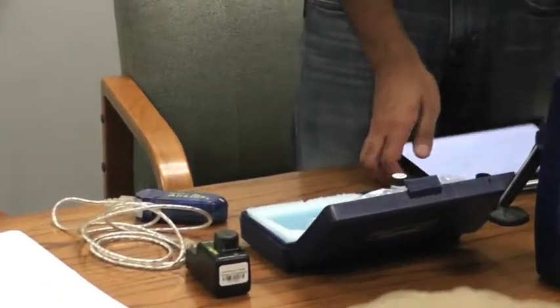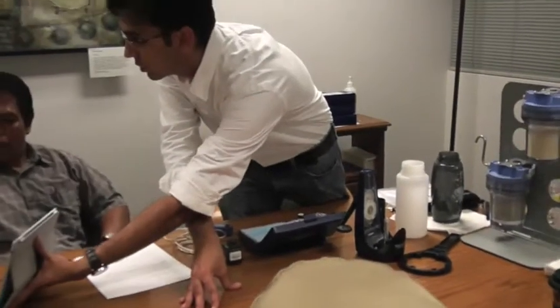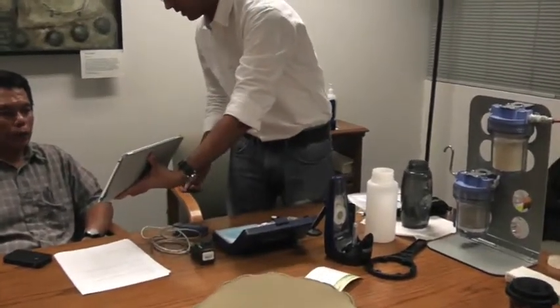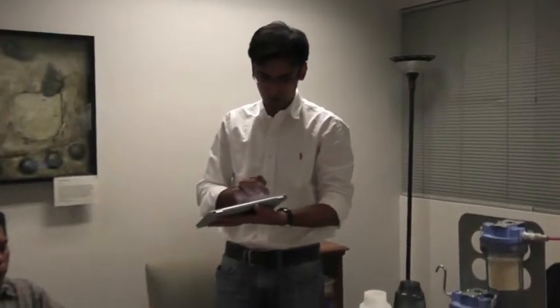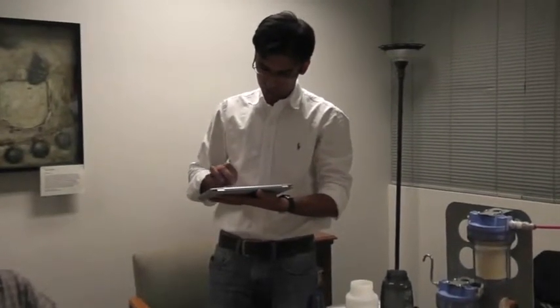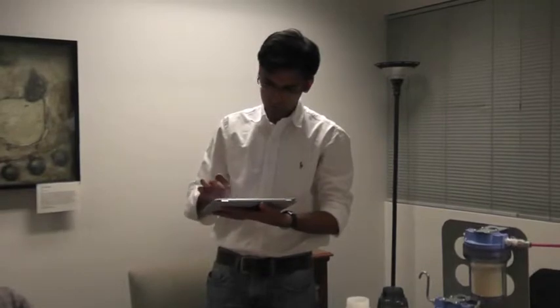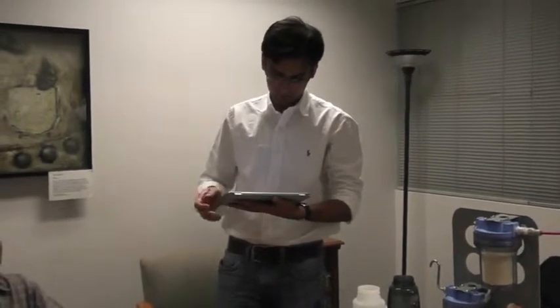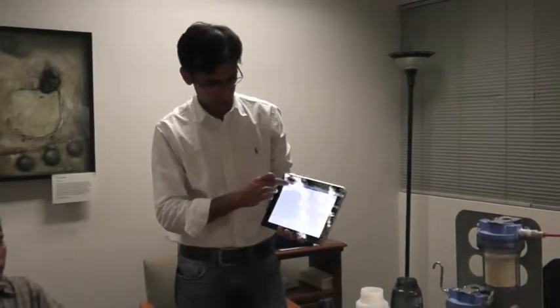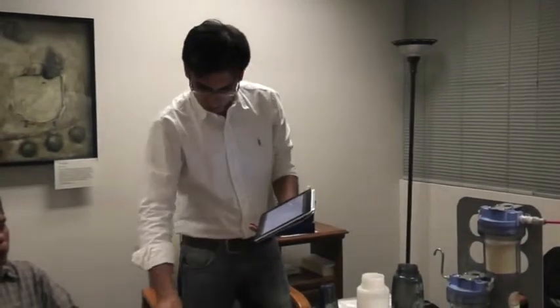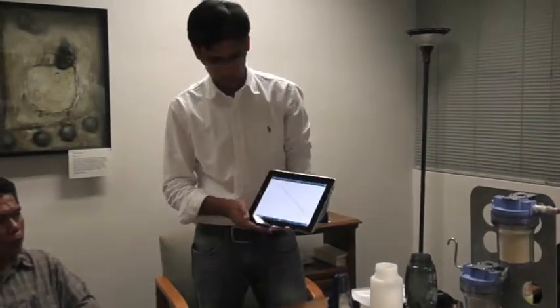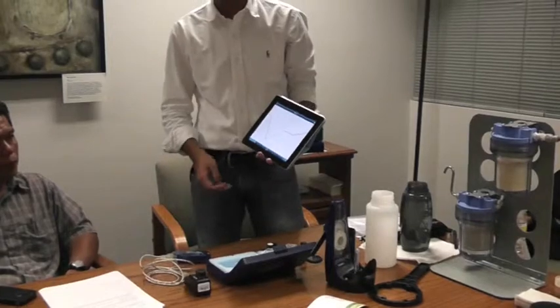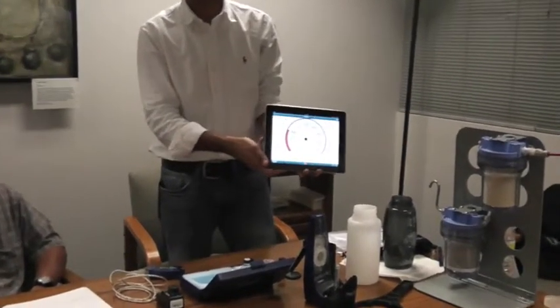Just close that. So you add your experiment again. This time it automatically recognizes that the turbidity meter is connected, so you don't really have to set anything on this. It's automatically recognizing that it's turbidity. Okay, so title, I'll add turbidity this time. Click that for the experiment interface to pop up. Okay, that's set, and then let's record. So there you go, your graph, because that's the 100 NTU vial that I put in. So see, around 100. The reading is 101.55.